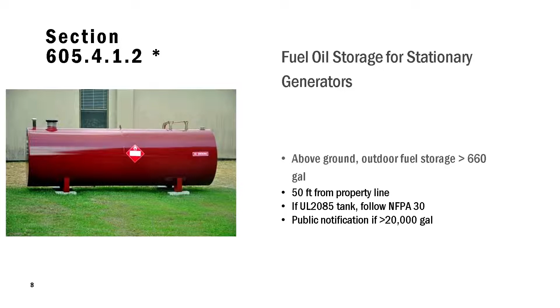For fuel oil storage for stationary generators, we changed that for exterior. Some of the risk modeling that the hazmat group looked at, we were able to look at the hazard and maybe reduce that a little bit. So for any above ground outdoor fuel storage over 660 gallons, the requirement is that it's got to be 50 feet from the property line. If it is in a 2085 tank, then we need to follow NFPA 30 guidance. And if there is over 20,000 gallons, then it's a public notification requirement.